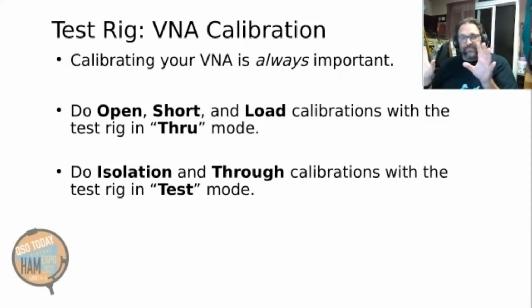Just trust me on this, and make sure you're calibrating it over the full range of frequency that you're going to be running your tests at. If you calibrate it for just the 20-meter band and then measure over the entire HF spectrum, that's not going to work out so well. Ask me how I know.